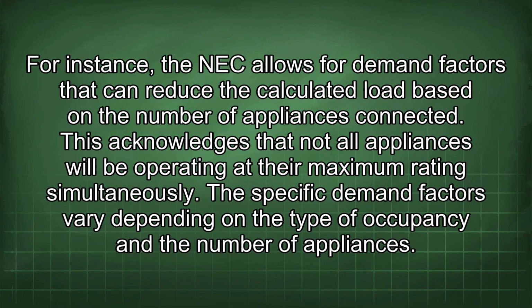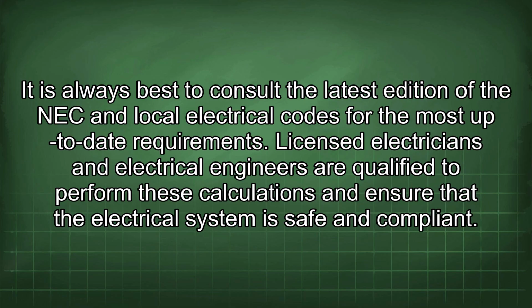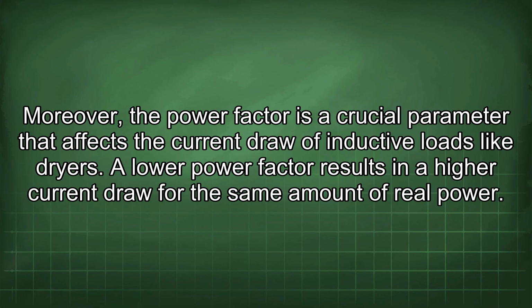For instance, the NEC allows for demand factors that can reduce the calculated load based on the number of appliances connected. This acknowledges that not all appliances will be operating at their maximum rating simultaneously. The specific demand factors vary depending on the type of occupancy and the number of appliances. It is always best to consult the latest edition of the NEC and local electrical codes for the most up-to-date requirements. Licensed electricians and electrical engineers are qualified to perform these calculations and ensure that the electrical system is safe and compliant. Moreover, the power factor is a crucial parameter that affects the current draw of inductive loads like dryers. A lower power factor results in a higher current draw for the same amount of real power.